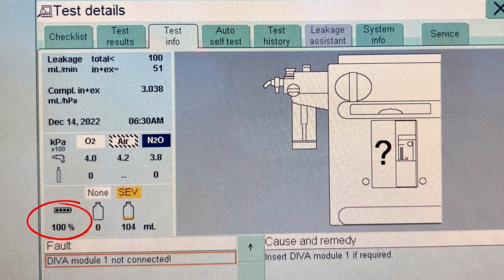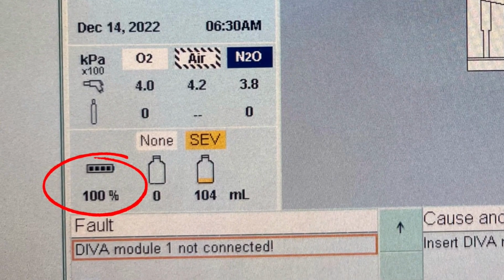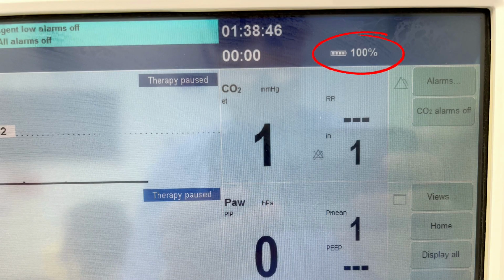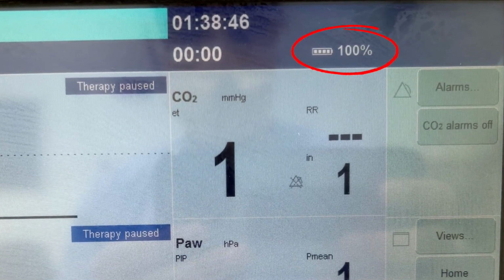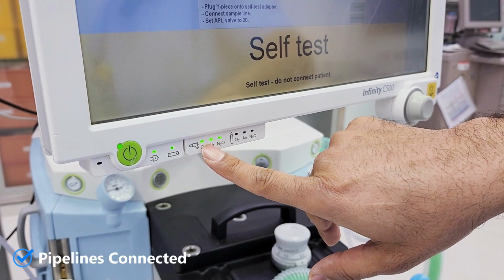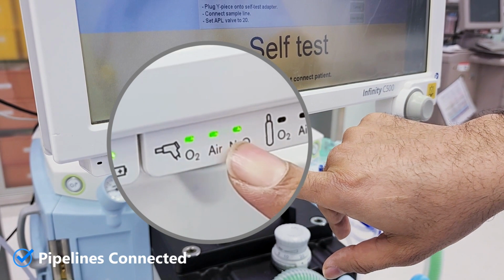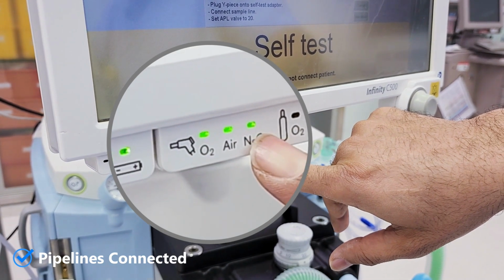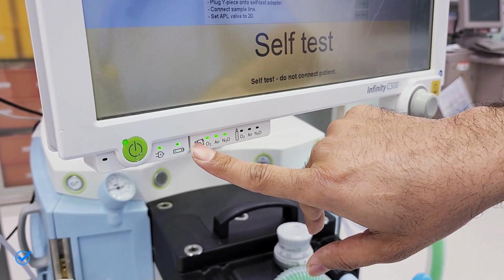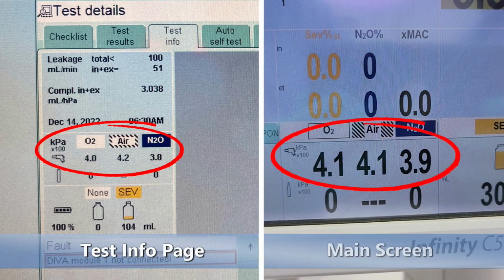You can see the battery level percentage from the test info page. Also, the percentage of the battery will be visible on the top right corner of the screen during the case. These solid, green LED indicators confirm that the pipelines of oxygen, air, and nitrous oxide are connected, and pressure is sufficient. The pipeline pressure can be seen on the main screen.